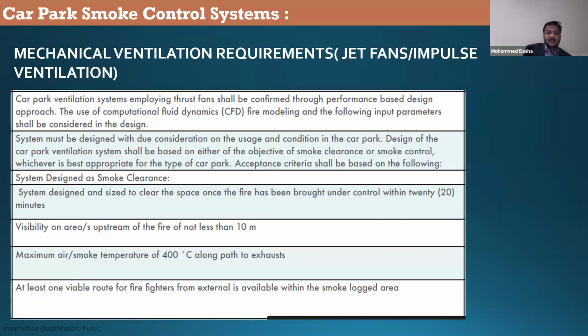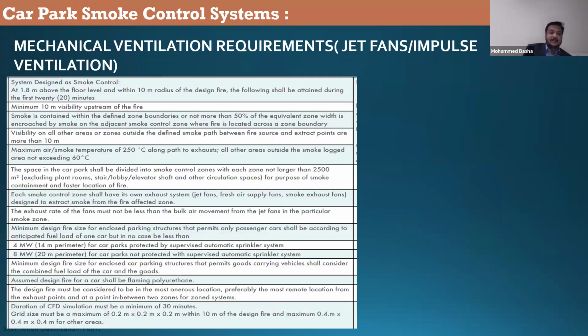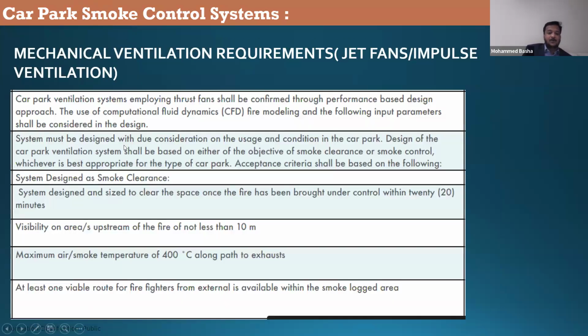Okay, here is the important thing: mechanical ventilation requirements for a jet fan system. This jet fan system can be designed for smoke clearance as well as smoke control. What is smoke clearance? I told you before, it is a purging system, meaning the system operates after the fire to clear the smoke out of the area. So there are no tenability requirements here, no temperature requirements for occupants.